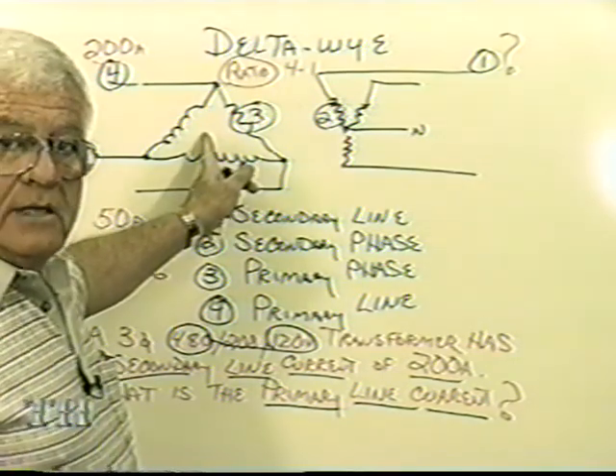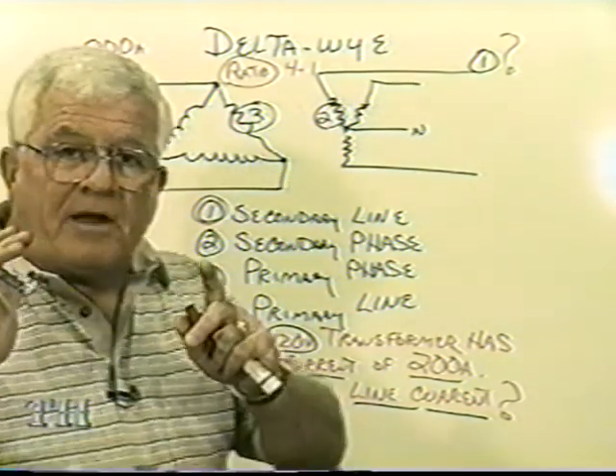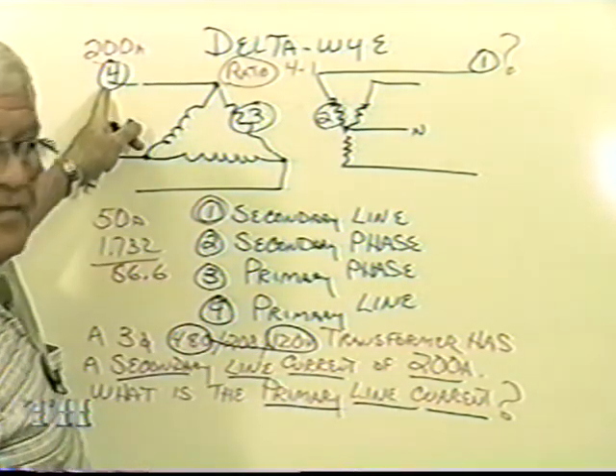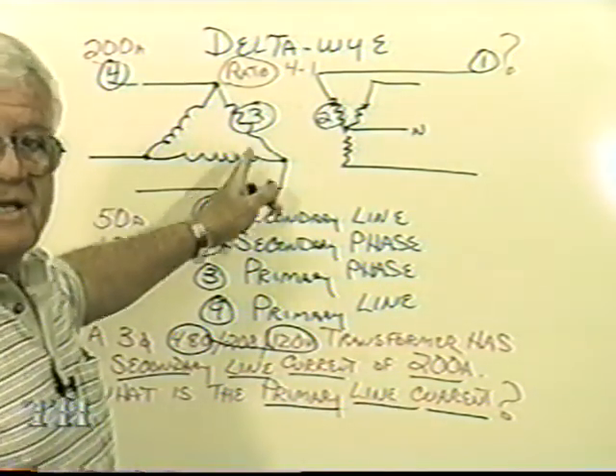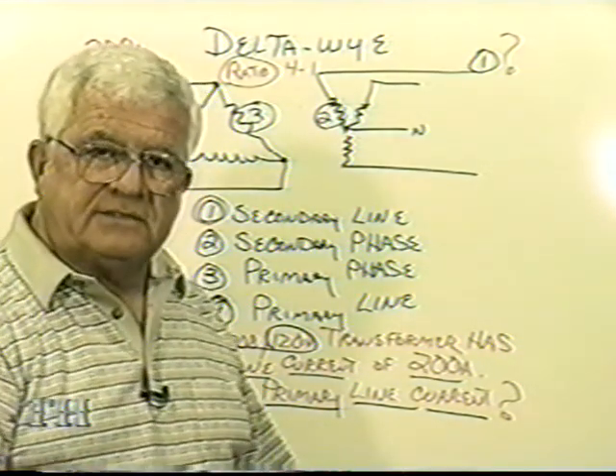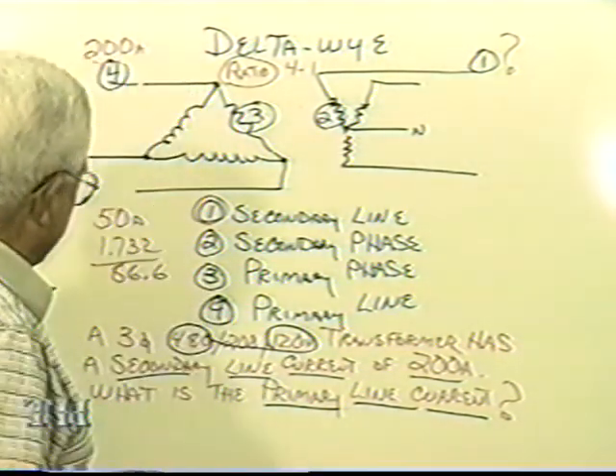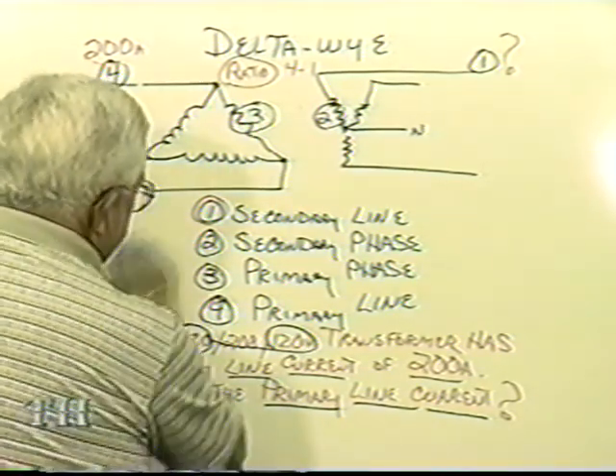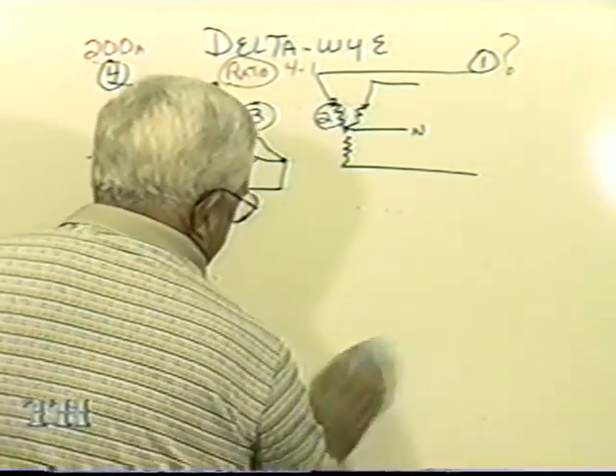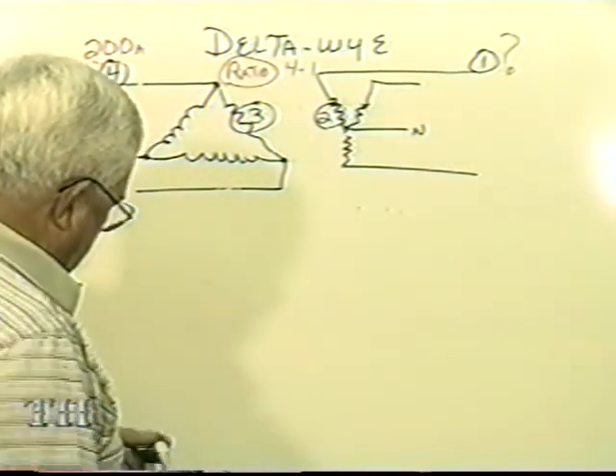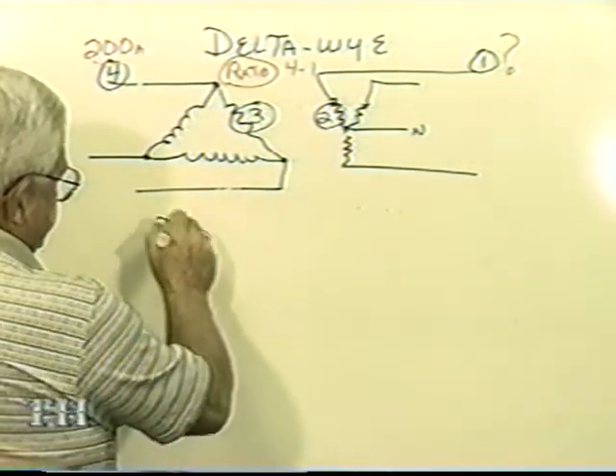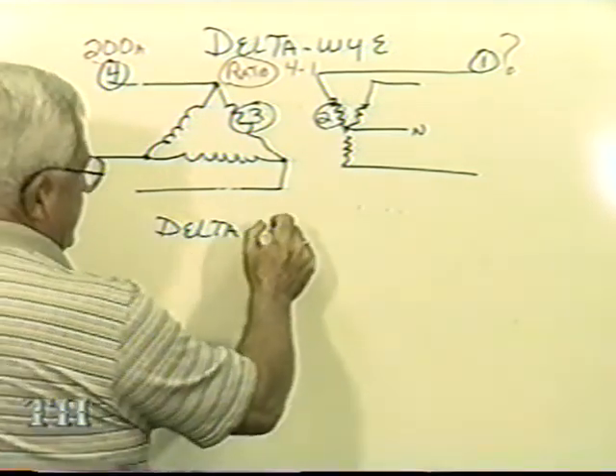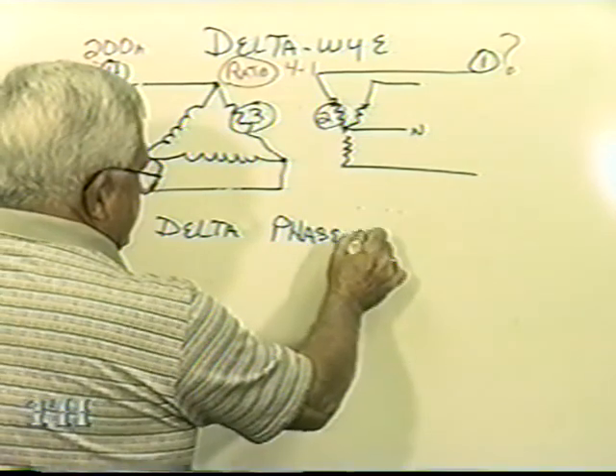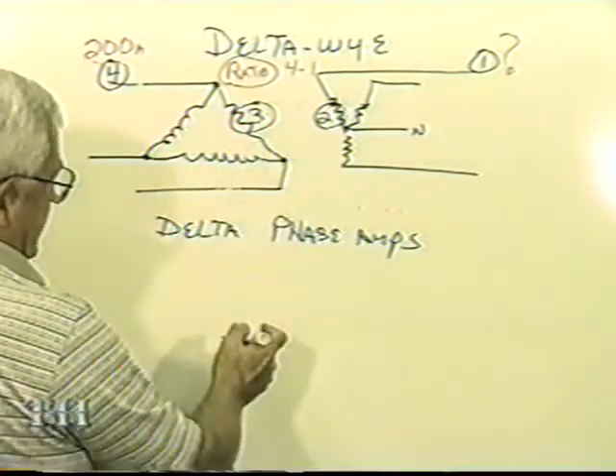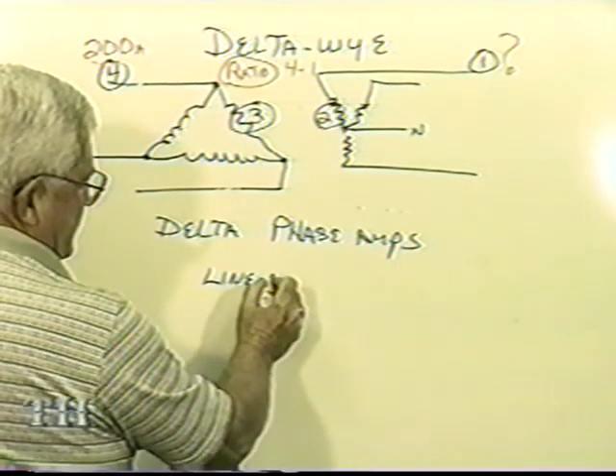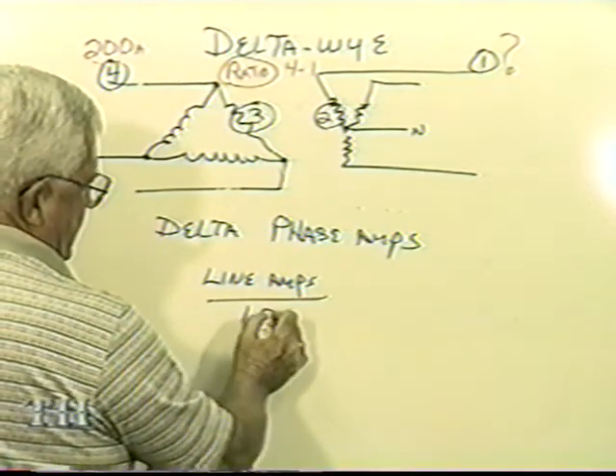Is this a delta or a Y? It's a delta. I go to my format for delta. Watch, this is the line. The first thing I got to know is the phase. I got to go from line down to phase in a delta. We learned earlier that we would have to take, watch, if I wanted to know delta phase amps, in other words this is what I want to know, phase amps, I would have to take the line amps - this is what your format says - and divide that by the square root of 3.